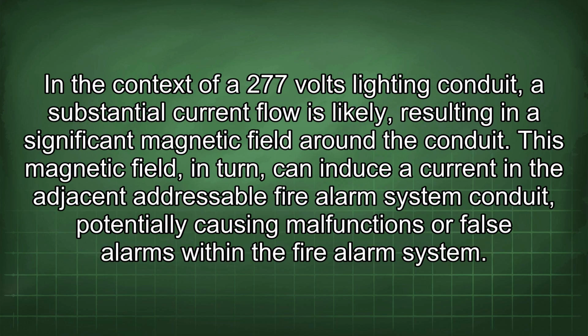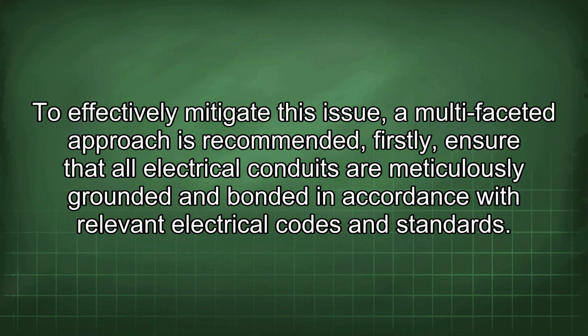In the context of a 277 volts lighting conduit, a substantial current flow is likely, resulting in a significant magnetic field around the conduit. This magnetic field, in turn, can induce a current in the adjacent addressable fire alarm system conduit, potentially causing malfunctions or false alarms within the fire alarm system. To effectively mitigate this issue, a multifaceted approach is recommended.